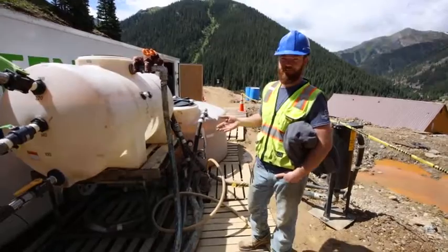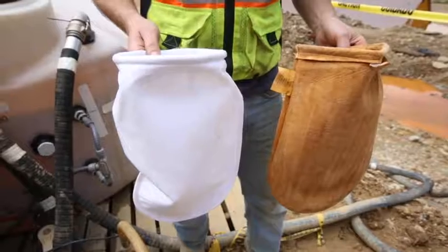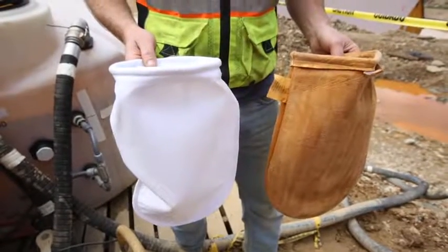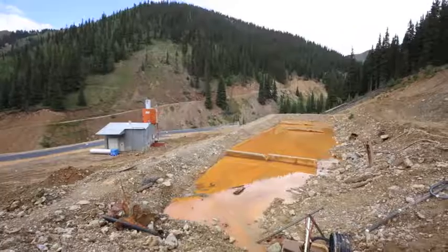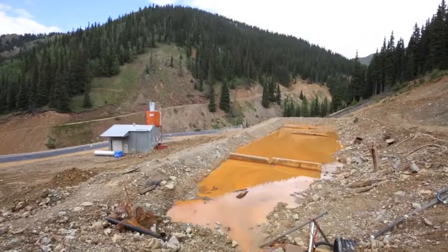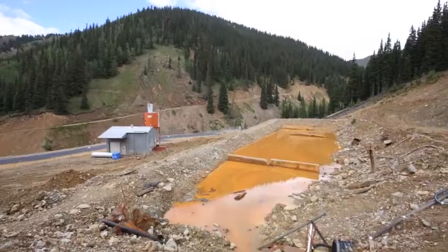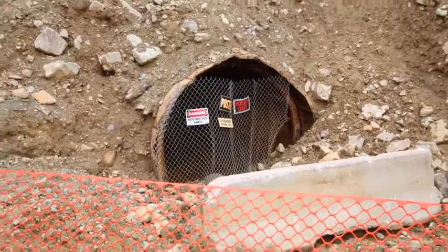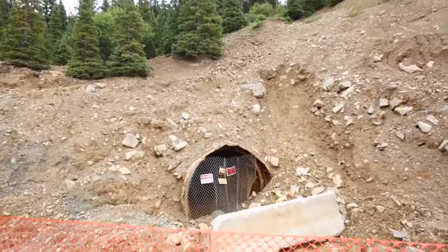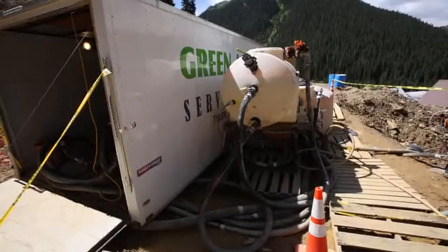On the runs we've had here, we had initial results to tune our system. We did a quick sample through the labs and were able to take out 90 to 95 percent of the dissolved metals that were in the acid mine discharge from the American Tunnel. We took out zinc by about 90 to 95 percent. Iron and other components such as calcium and magnesium were also greatly reduced in our run. Depending upon the metal, the effectiveness can vary slightly.